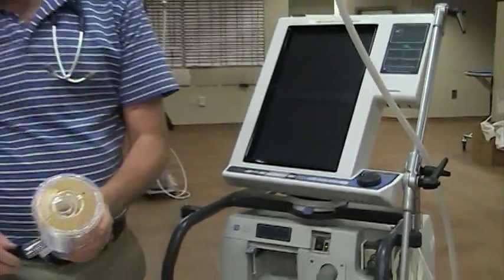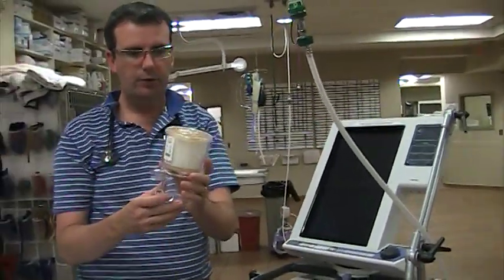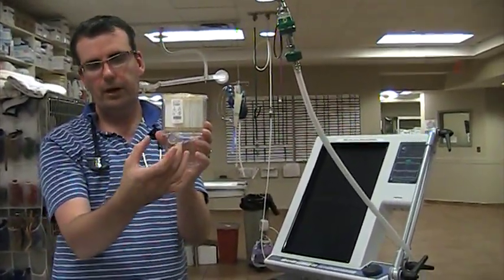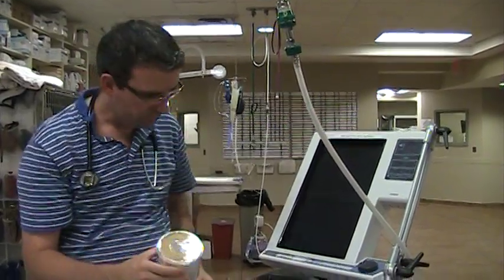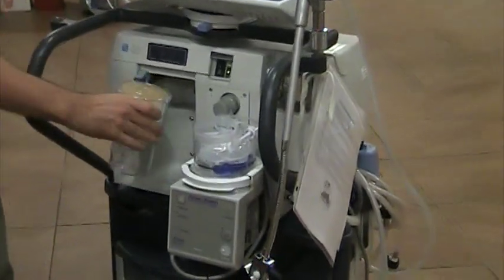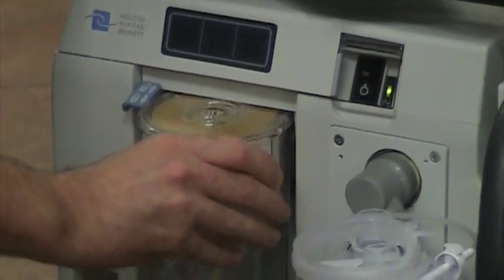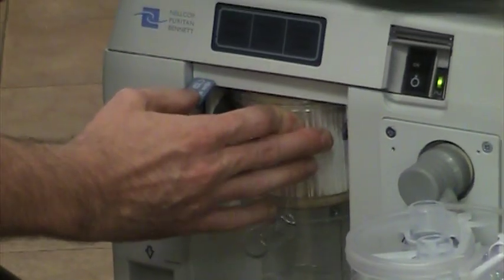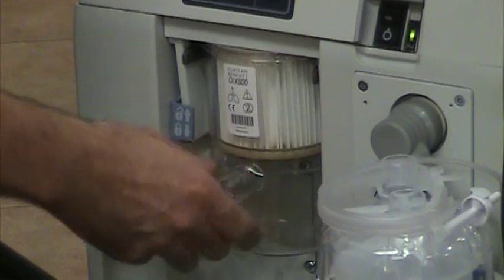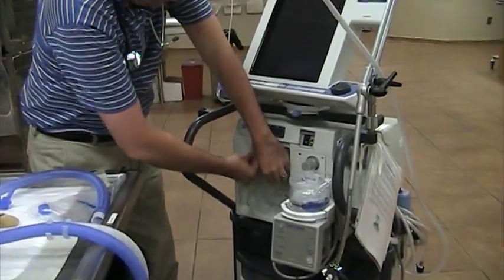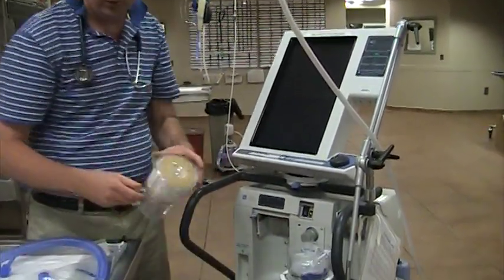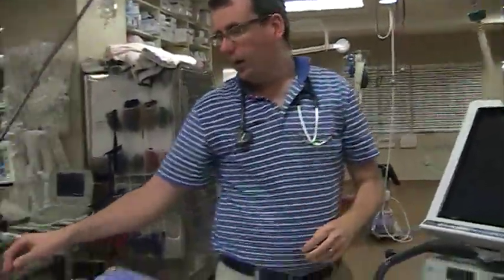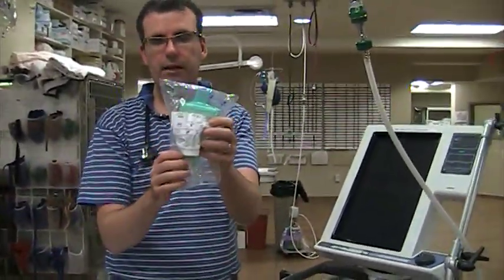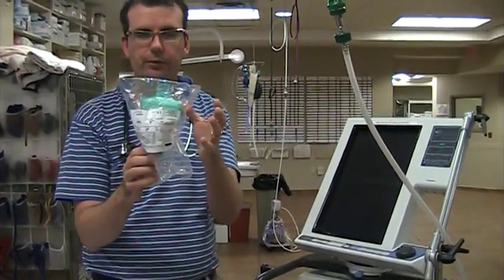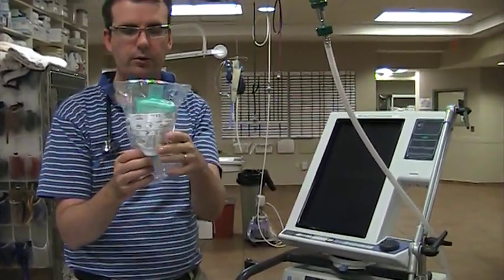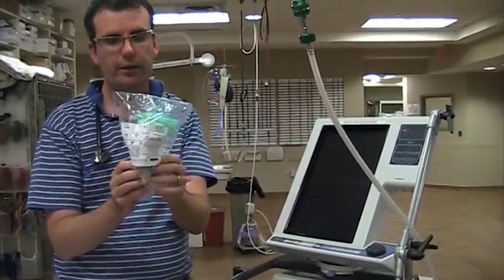This is the adult expiratory filter. This is the part where the expiratory tubing fits on. So you can see that this is already in the up position. This just slides in there nicely like that, and then you push that down to lock it in. So it's locked in. This is for the adult, and usually adult we consider anything greater than 10 kilos. This is the neonatal set, so anything in that 5 kilogram or less range, or you potentially could even use it for the 10 kilo or less range.